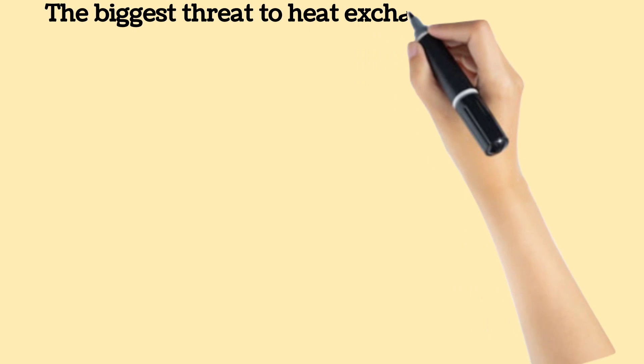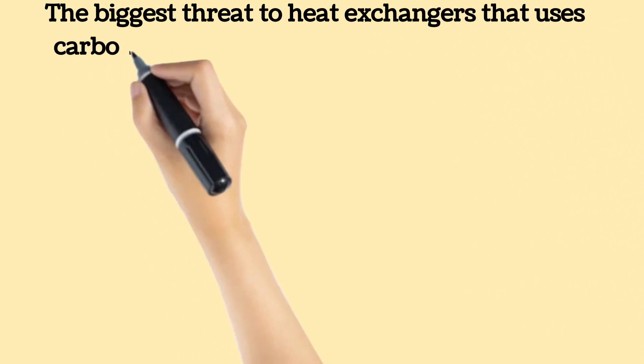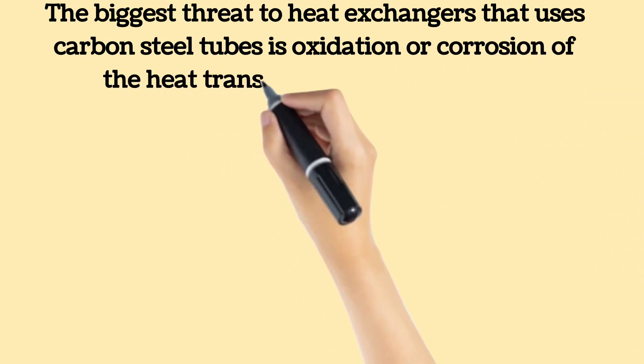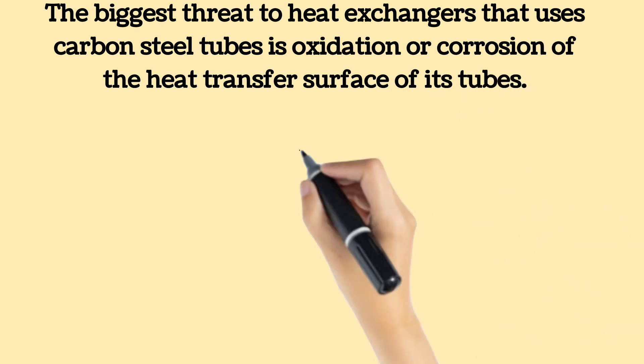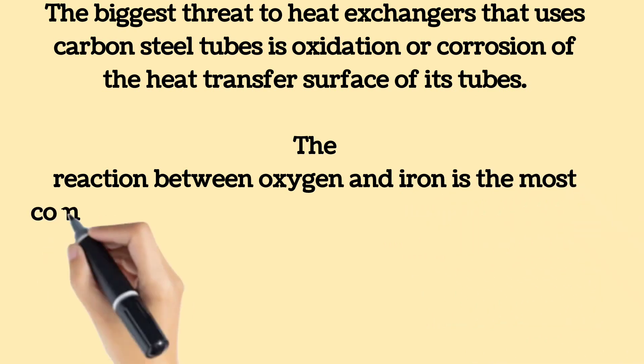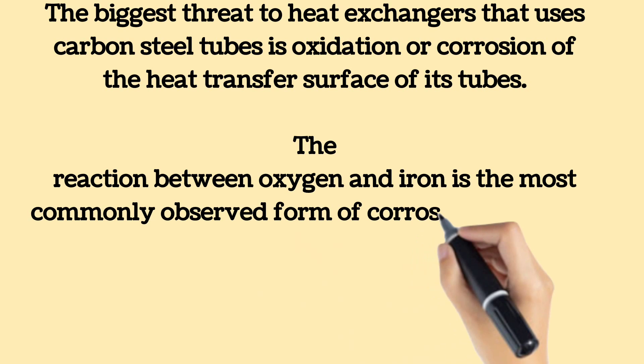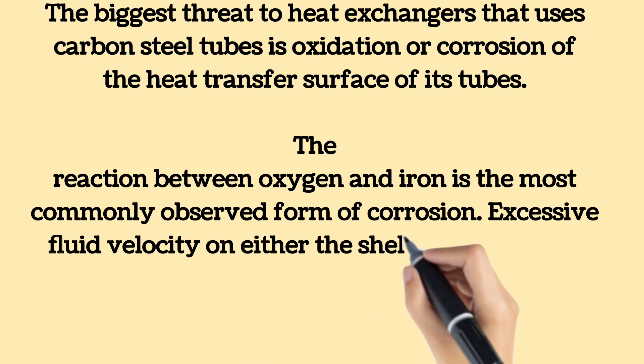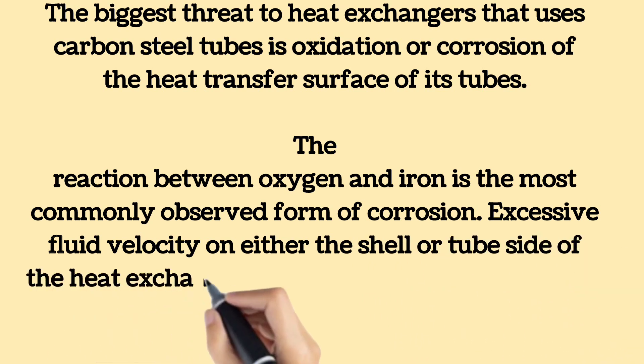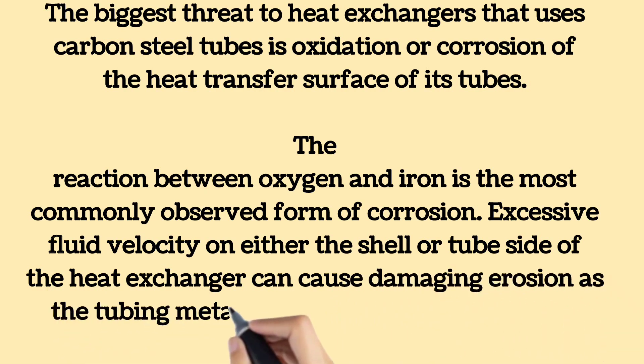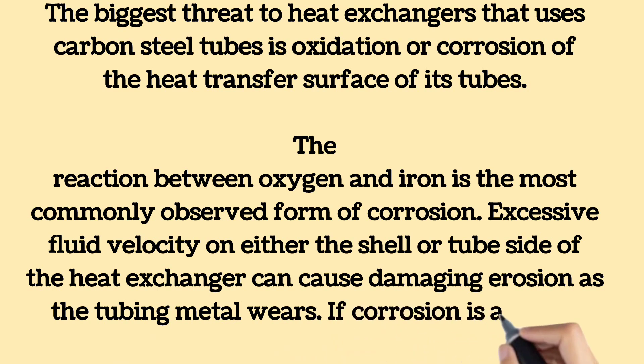The biggest threat to heat exchangers that use carbon steel tubes is oxidation or corrosion of the heat transfer surface of the tubes. The reaction between oxygen and iron is the most commonly observed form of corrosion. Galvanic corrosion is common in shell and tube heat exchangers at the contacts between the tubes and the baffles or tube sheets when different metals are used for those parts. Excessive fluid velocity on either the shell or tube side can cause damaging erosion as the tubing metal wears, and if corrosion is already present it can be accelerated, as erosion has the potential to remove the tube material's protective film, exposing fresh metal to further attack.